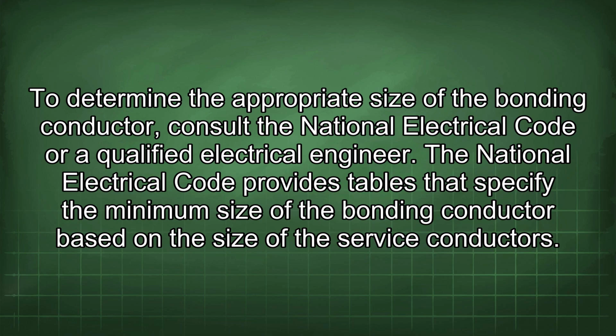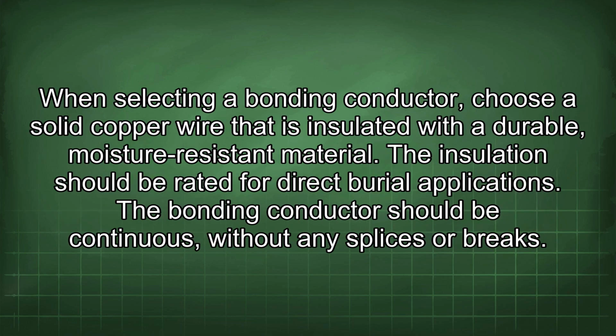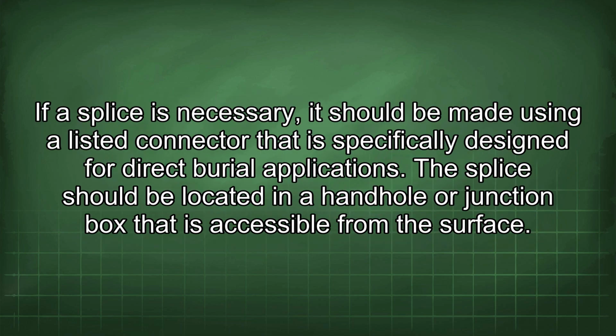When selecting a bonding conductor, choose a solid copper wire that is insulated with a durable, moisture-resistant material. The insulation should be rated for direct burial applications. The bonding conductor should be continuous, without any splices or breaks. If a splice is necessary, it should be made using a listed connector that is specifically designed for direct burial applications. The splice should be located in a handhole or junction box that is accessible from the surface.